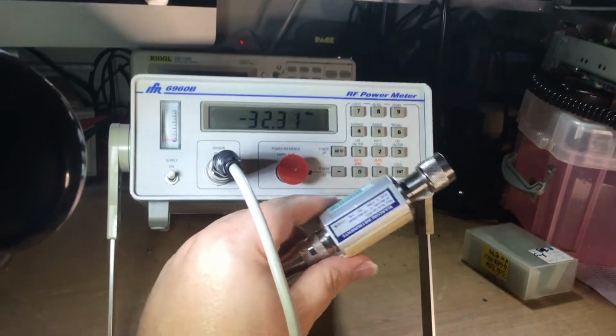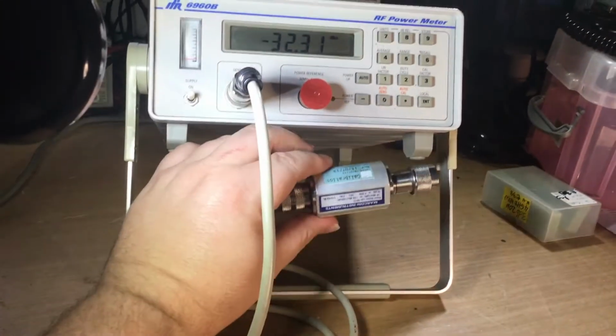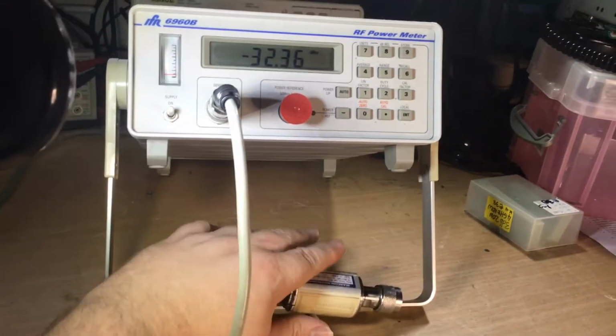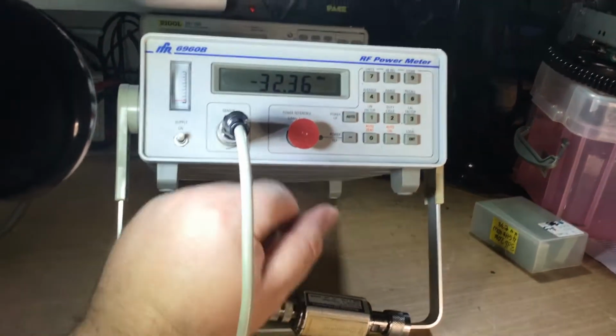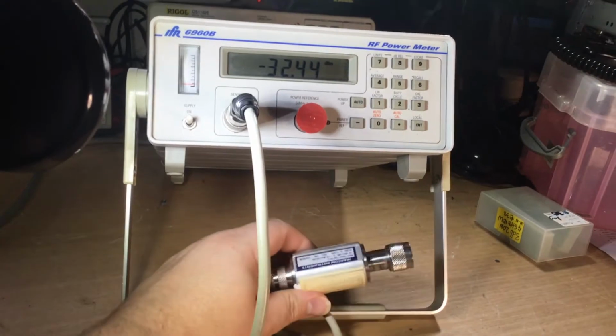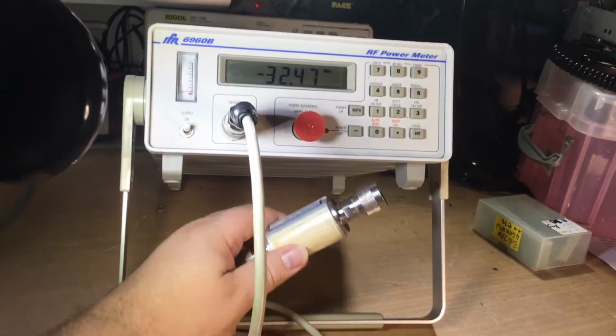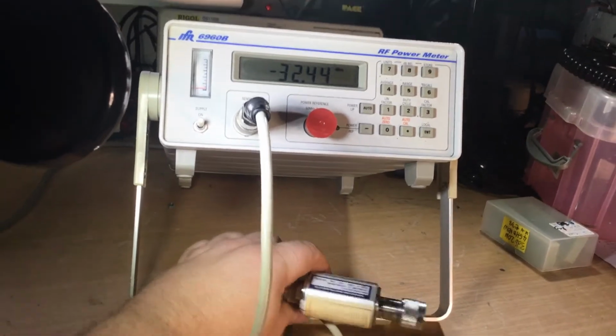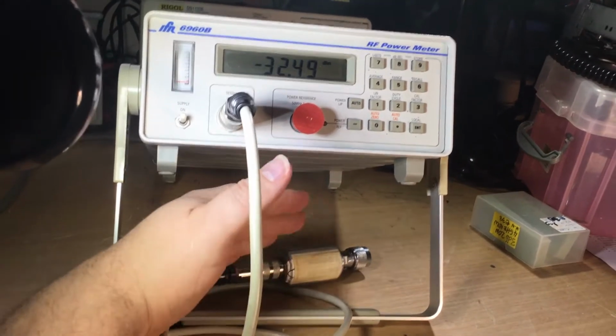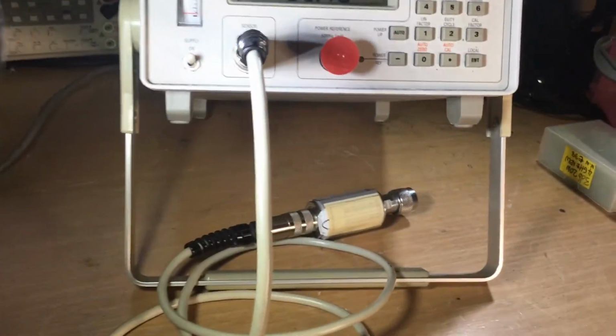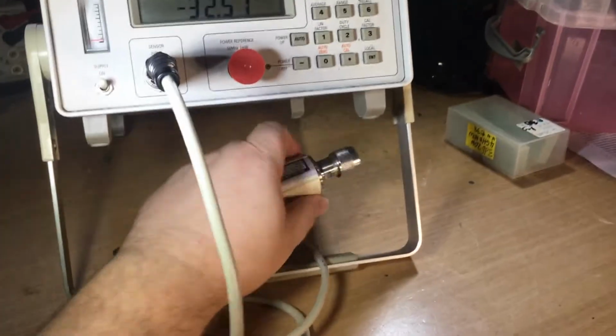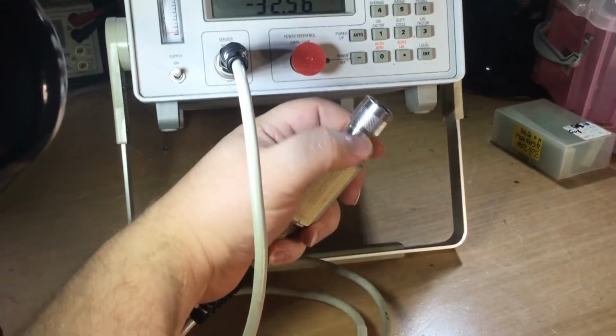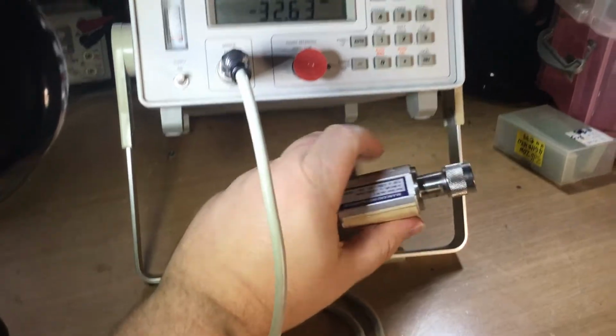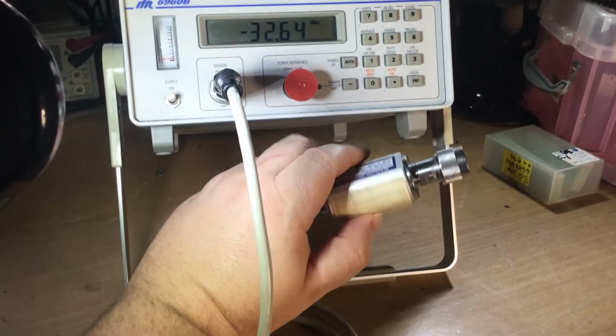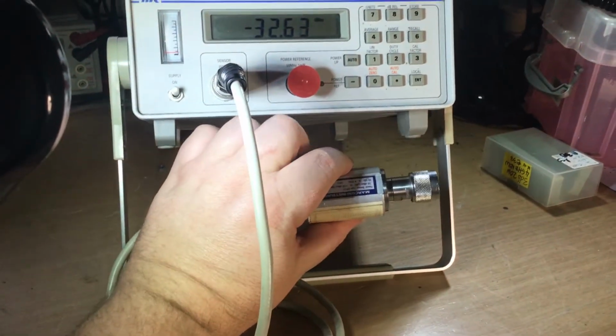Now this particular sensor goes up to about 4.2 gigahertz. The other ones that I've got, which you've seen in the other videos, go up to about 20 gigahertz, 26 gigahertz and 46 gigahertz. And generally these only measure power in the milliwatt range. There are some sensors that you can get where they have heatsink fins here on the collar of this N-type plug, and they can measure up to a couple of watts CW, but generally speaking they don't measure high power RF.